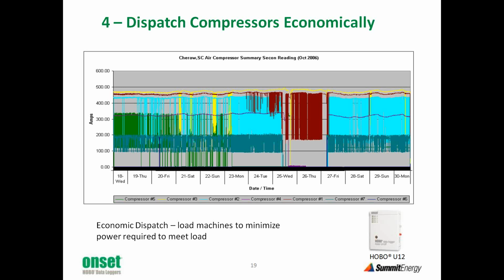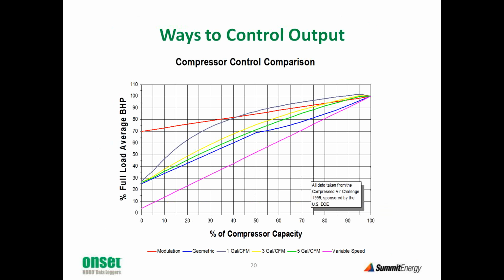Now, the reason this is important is that that's an inefficient way to supply the air. If you fix the controls on these air compressors, you could reduce the cost of producing that air. This is just a reminder that there are a number of ways to control air compressors. Somebody needs to modulate. You can't just let all the air compressors run at their most efficient point. Then there would be no pressure control. So we have to have one machine that's changing its output in order to maintain the pressure set point.